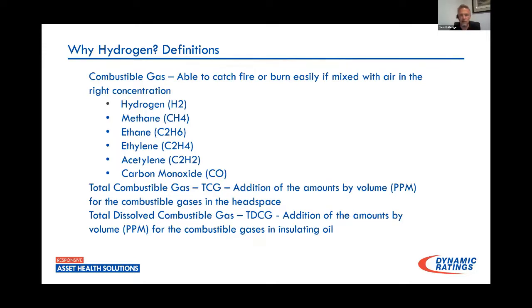So how do I know? So hydrogen monitoring starts with, that's a smoke detector. And that's any hydrogen monitoring on any transformer. There's not a lot of analytical value to be gained from looking at hydrogen alarms. That just kind of tells you something's going on, kind of like your smoke detector tells you something's on fire in your house. It doesn't say which room it's in. So when we get these alarms, we need to get these transformers out of service. Let's go out, let's pull some DGAs, let's do some offline testing to determine where our problem's happening.